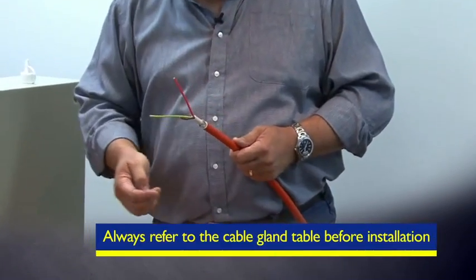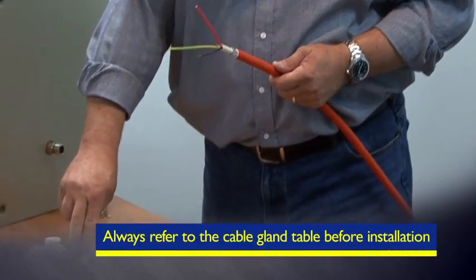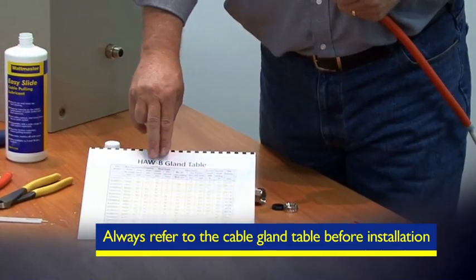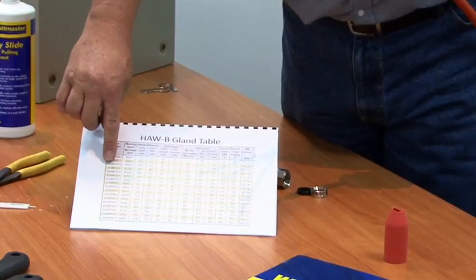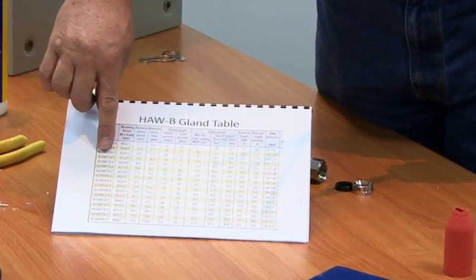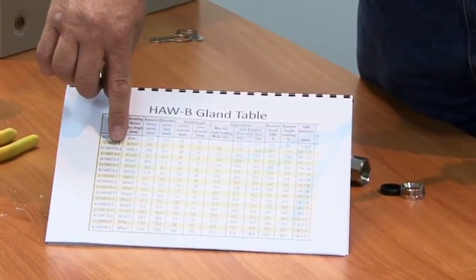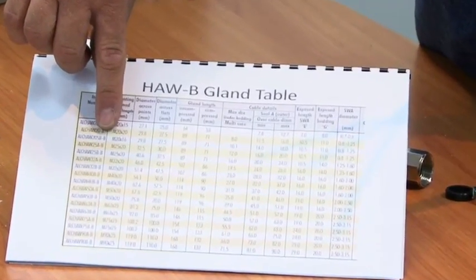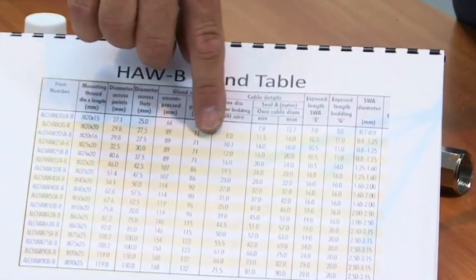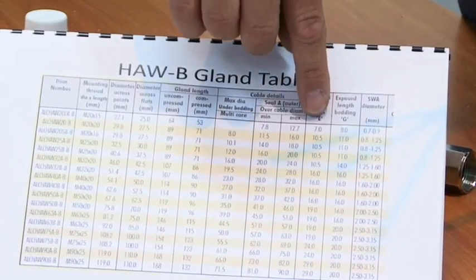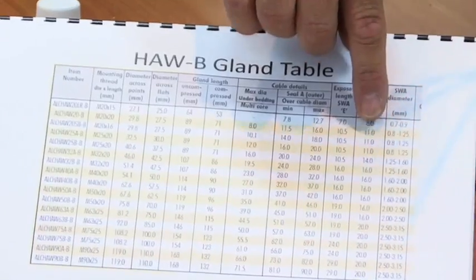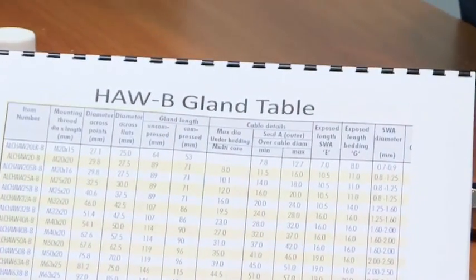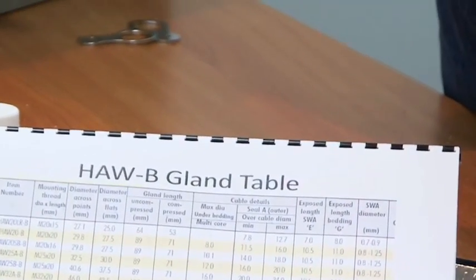If we look at our HAW-B gland table, you'll note the difference in part number: ALC HAW-20B-B, with B being barrier. Looking at the fitment details, it's the same for the cable and same length of exposed steel wire armour, but we've got another bedding dimension here, G, which is 11 millimeters long. Instead of having an arbitrary length here, this is another critical dimension we must consider.